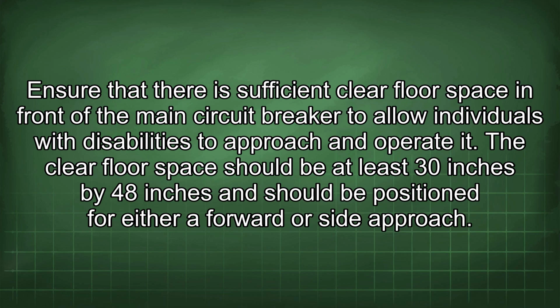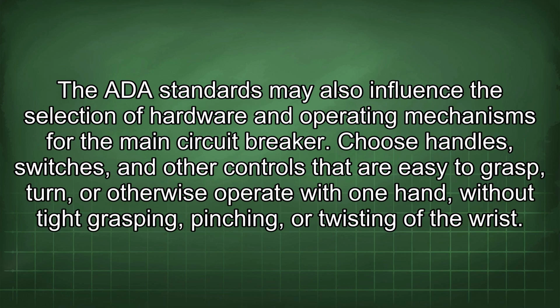Ensure that there is sufficient clear floor space in front of the main circuit breaker to allow individuals with disabilities to approach and operate it. The clear floor space should be at least 30 inches by 48 inches and should be positioned for either a forward or side approach. The ADA standards may also influence the selection of hardware and operating mechanisms for the main circuit breaker. Choose handles, switches, and other controls that are easy to grasp, turn, or otherwise operate with one hand without tight grasping, pinching, or twisting of the wrist.